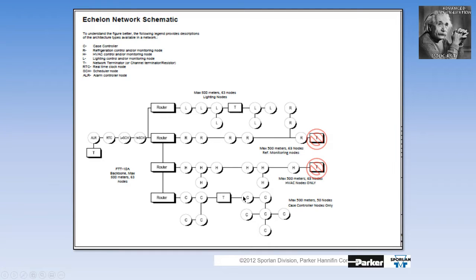Just to give you an idea of how open our network is, as long as you stay within the Echelon parameters, we allow you to design the hardwired network to use the least amount of cable possible, because Echelon cable is a little more money than standard communication cable. So we want the least amount of cable possible, and balanced resistance on each network channel. Never put the resistor at the end of the line, always find the middle of the network.